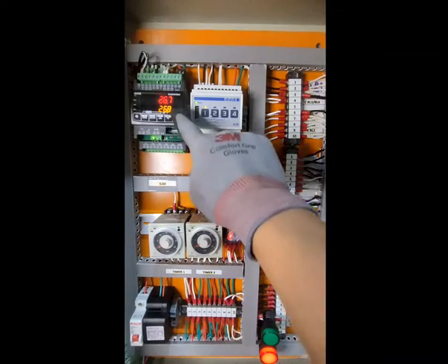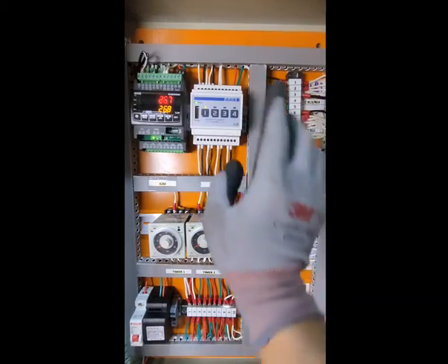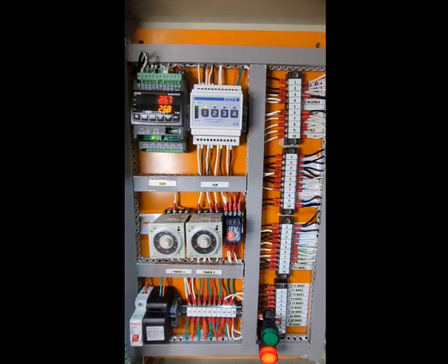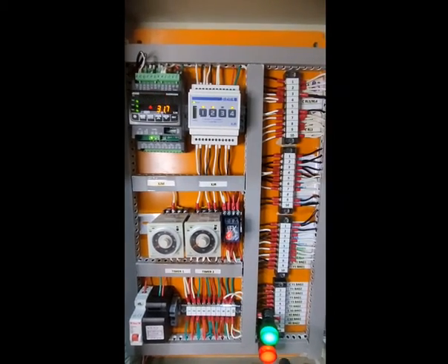As I said earlier, whenever there's a temperature rise in the room, which means there's a problem, maybe the unit that is supposed to run is not running, so the auto changeover panel will force the other unit to turn on. When this temperature reaches around 31 degrees C, it will trigger an alarm and force the second unit, the resting unit, to turn on.